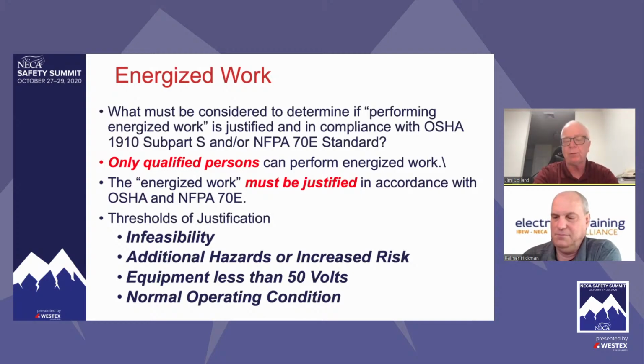That's where we see most of our justified energized work, because it's task driven, which means I cannot perform my task unless I do it energized. So the best example there would be troubleshooting or measuring voltage, because we have some type of a problem. If I shut it off, I'm not going to be able to perform my task.